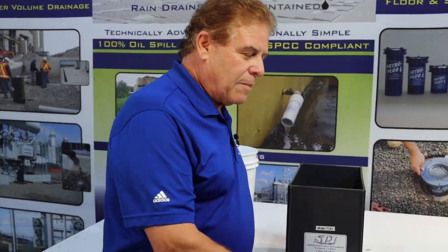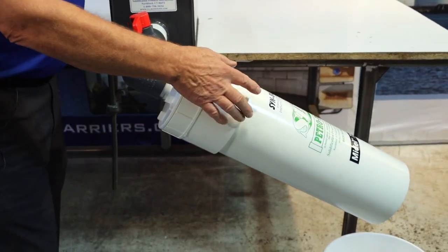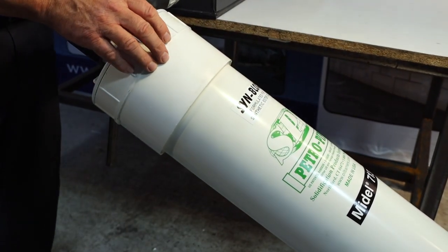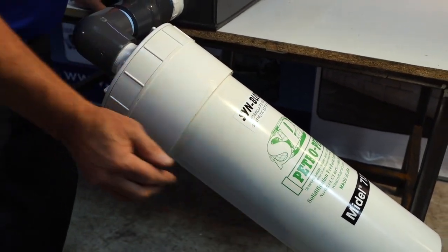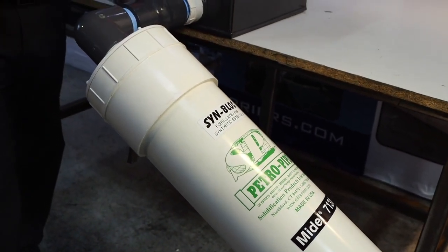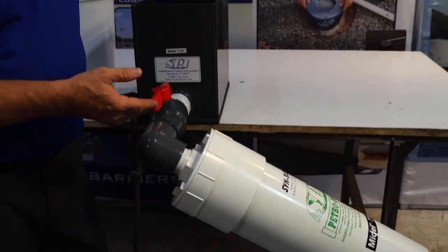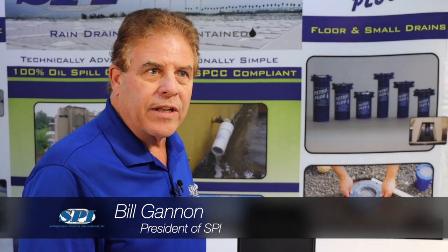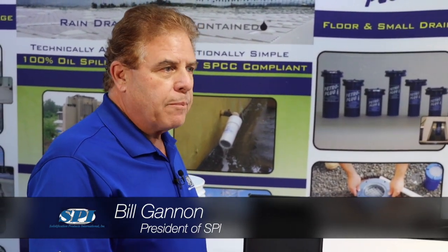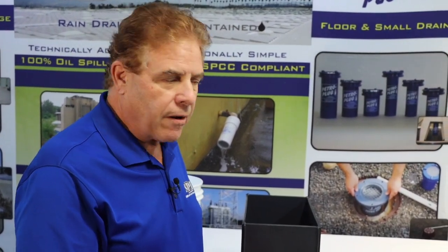This is our PI620 Synthetic Ester SynBlock Petropipe, manufactured specifically for synthetic ester fluids — this one is particularly for Model 7131. A lot of large power transformers are looking at the benefits of synthetic ester fluid over regular transformer oil, due to the fact that it provides a much higher flashpoint, so it's better for fire safety.